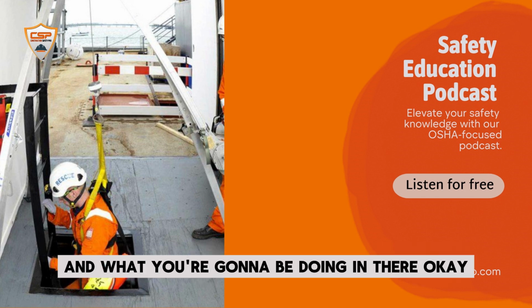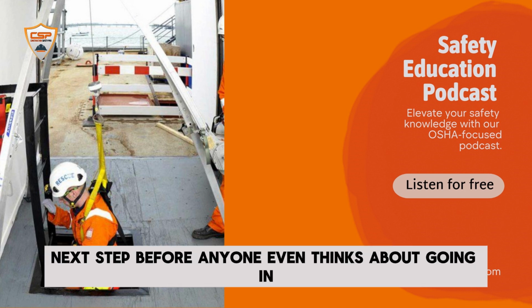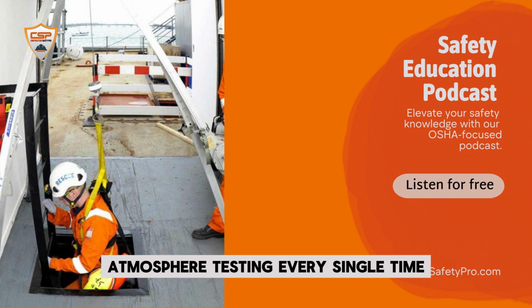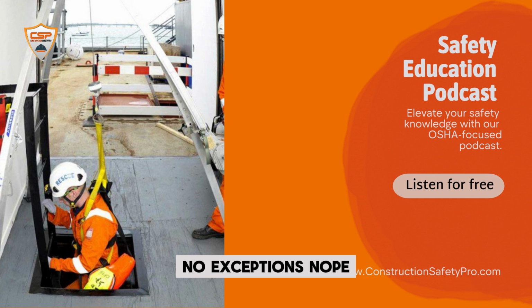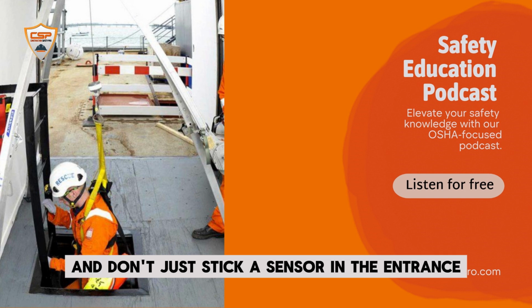Okay, so we've done our risk assessment, and what's that absolute must-do next step before anyone even thinks about going in? Atmospheric testing, every single time. No exceptions? Nope. You can't just go on your gut feeling or what you think might be true. You need hard data about that air. And don't just stick a sensor in the entrance and call it a day.